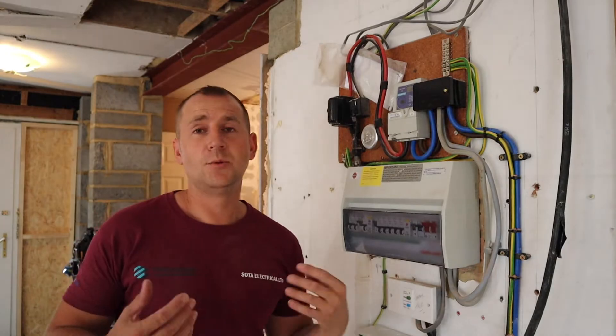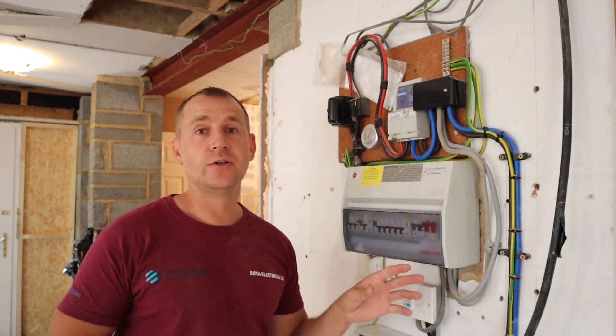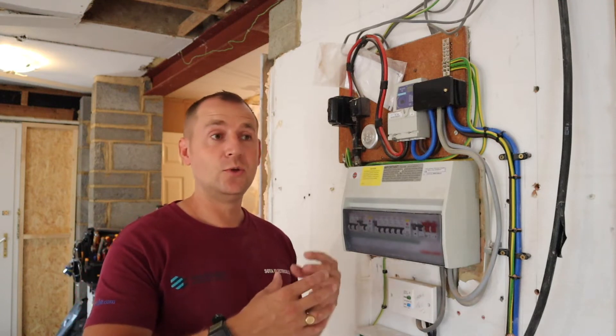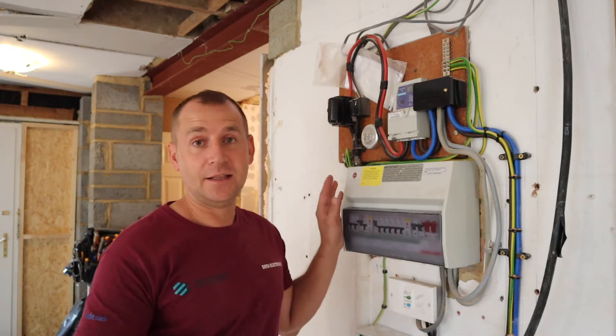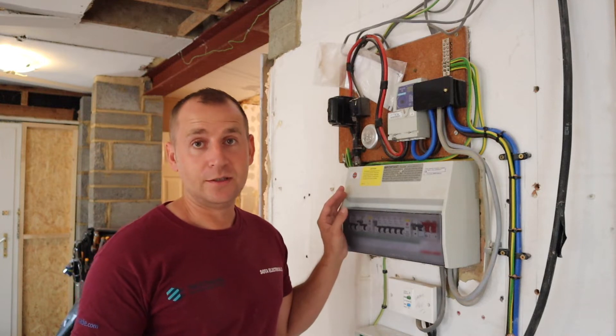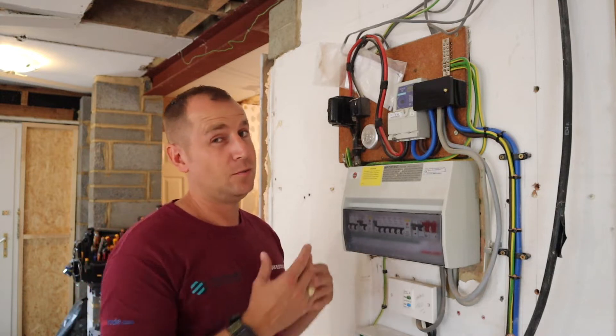I made a mistake. I'm on a job today where my clients are renovating their house, and that includes a full rewire. That part's been carried out by a different electrical contractor. When I did my quote, I stated that I would install a circuit into the existing consumer unit. There was a bit of miscommunication — my client took that as me being happy to install my EV charging point and terminate it in this consumer unit. That isn't really what I meant. I thought the new consumer unit would be in place before I came to install my charger. So I've turned up, and technically can I connect my charger into this one? Well, yes.